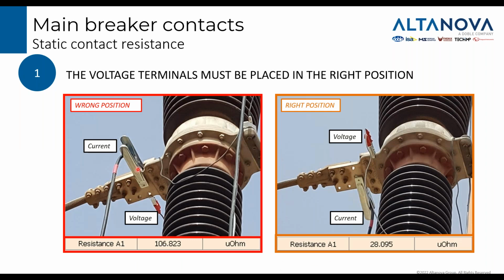Here you can see, this is the clamp for the current injection. This is just one of the 2 sides of the main contact. So you may think that if you place the voltage clamp anywhere, you will get correct results, but this is not true. This is the value that you get with the clamp in this position, and this is the value that you get with the clamp in this position. This is correct, this is very wrong.